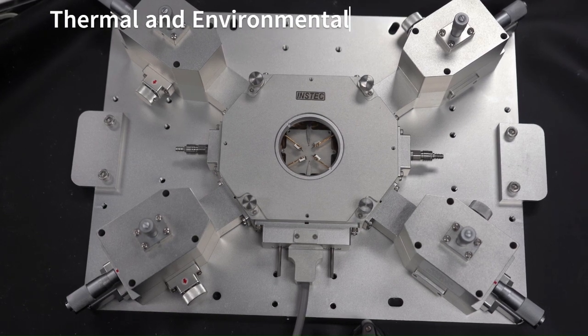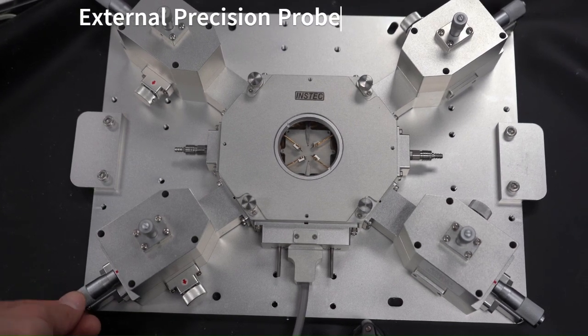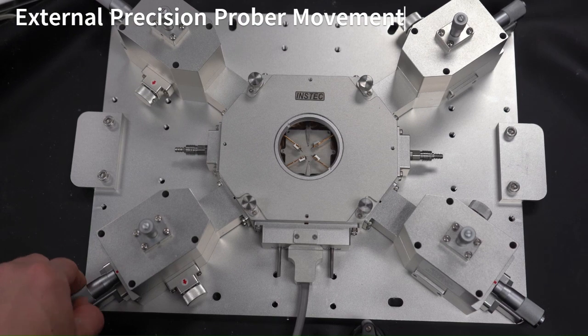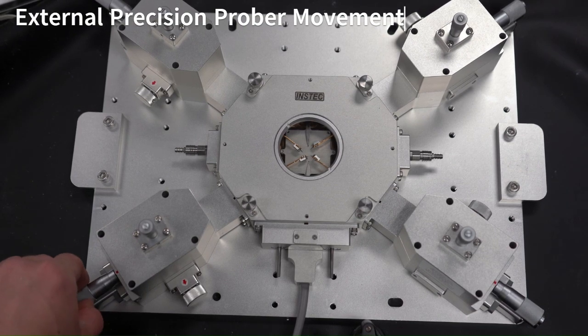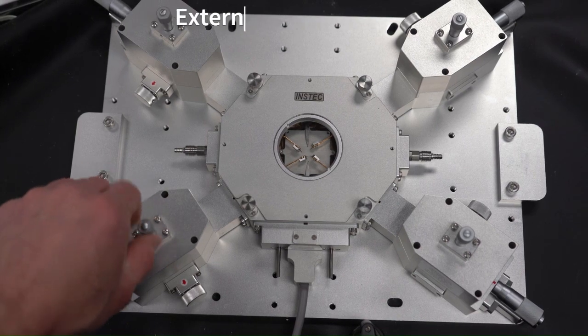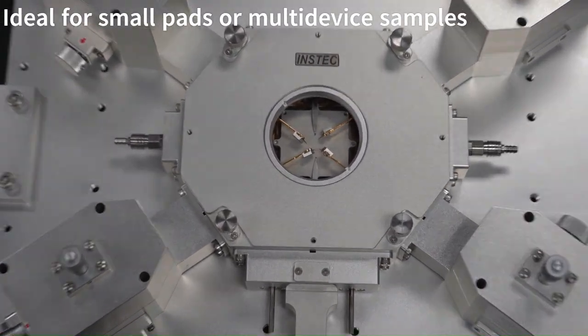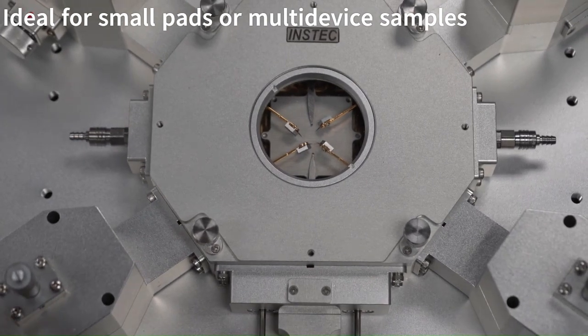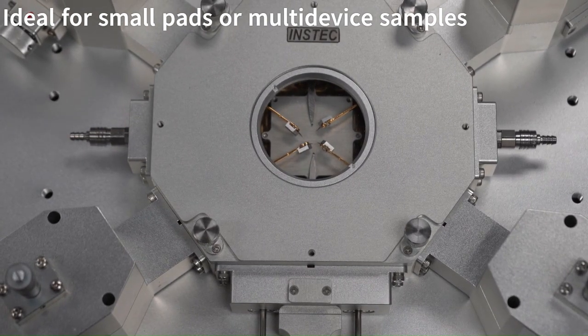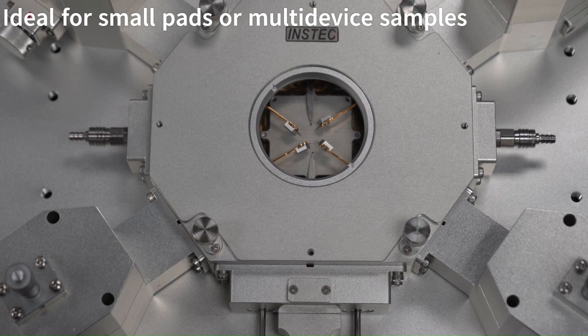This includes micromanipulators that externally can move probers in the X, Y, and Z direction, allowing you fine movement across your entire sample. You're able to land on exceptionally small pad sizes on the order of microns, all underneath a microscope, all in a well-contained environment.